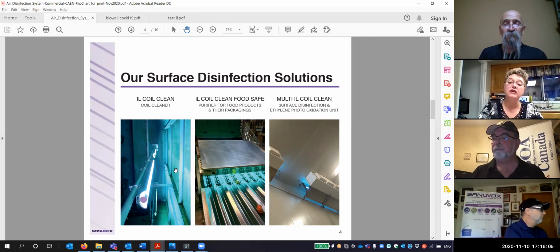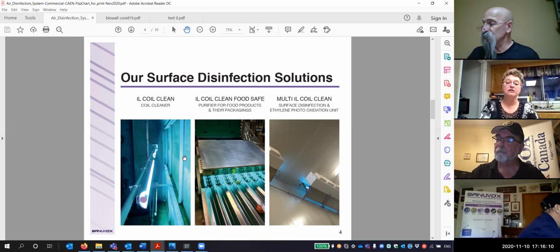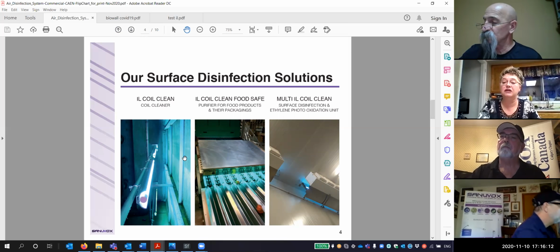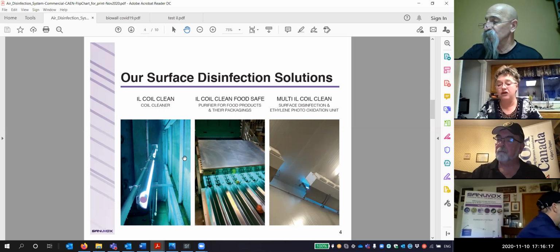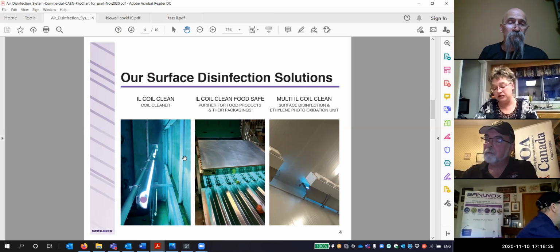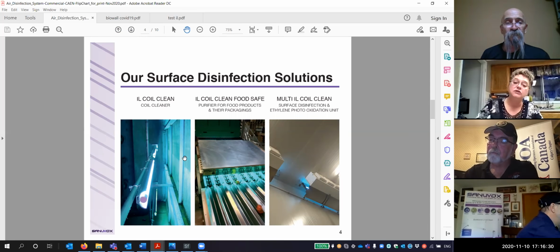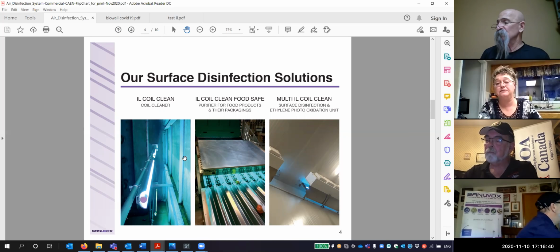So if you put UV on the coils, the first main advantage is the cost of running the AC drops dramatically. You don't have that compromising of the heat transfer. So your equipment's running more efficiently and at less cost to the building. Now, the other thing is that you drastically reduce the necessity to hire a refrigeration technician to come in and manually clean these coils and wash them out and use chemicals, because that UV will keep them clean.